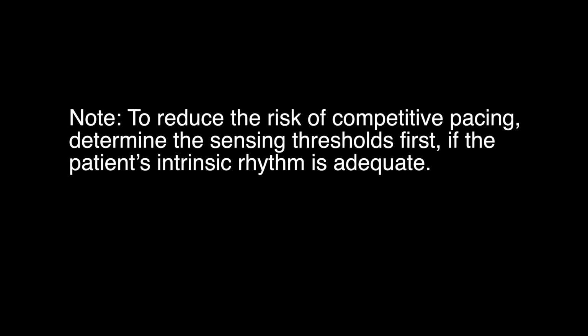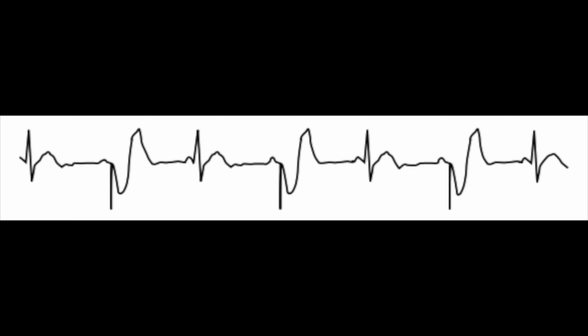Note: to reduce the risk of competitive pacing, determine the sensing thresholds first, if the patient's intrinsic rhythm is adequate. The temporary pacemaker detects the heart's own beat and does not deliver a pacing stimulus. Sensing threshold. The sensing threshold is the least sensitive mV setting at which the temporary pacemaker can detect a heartbeat. Monitor the patient's ECG and blood pressure as you follow the procedure to determine the atrial and ventricular sensing thresholds.